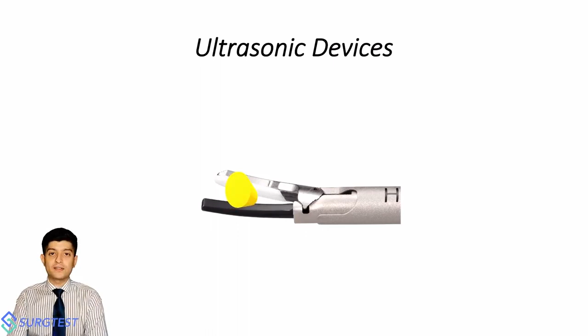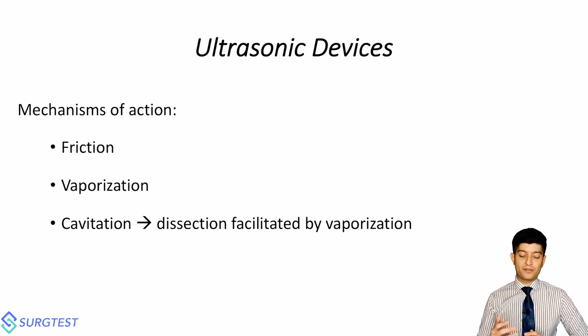So very quickly, there's friction at the end with some vaporization that occurs as a result of heating tissues close to 100 degrees Celsius, and cavitation occurs. Cavitation is essentially dissection that is facilitated by vaporization. When fluid within the tissues is vaporized, it ends up dissecting within the tissue spaces, causing the tissue to flare out and open up a little further. So that's the cavitation that we are sitting and talking about.